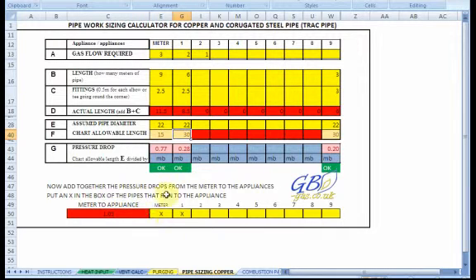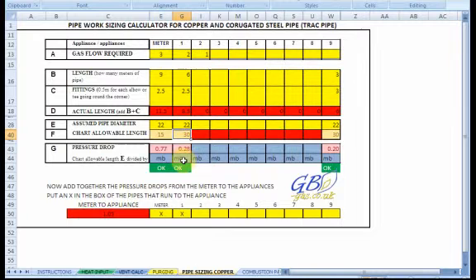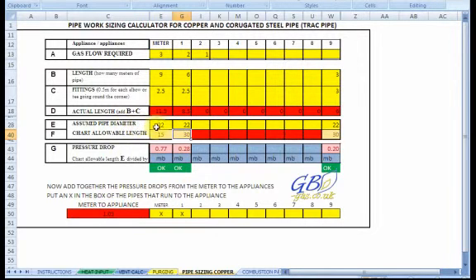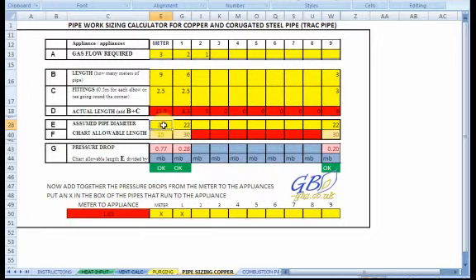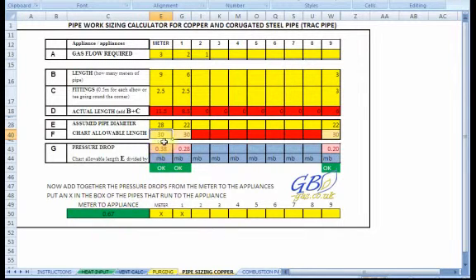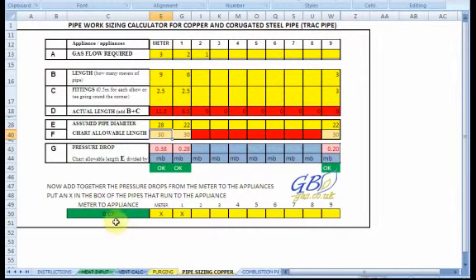So, I need to increase one of the pipe sizes. I wouldn't increase my second pipe going to the boiler, so I'm going to increase the pipe diameter of the first pipe coming from the metre. And we'll change it to 28 millimetre pipe. And you can now see that the drop has went down to 0.38 millibar drop, 0.28 for the second stage, and both of those added together gives me 0.67.